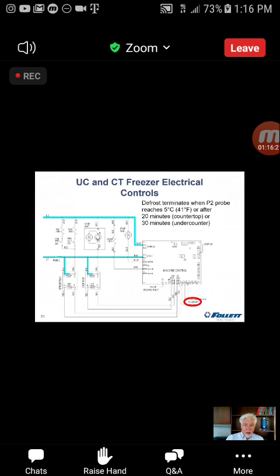Okay. So, like I said, we want to terminate on temperature. It typically takes around 7 or 8 minutes on these units. It should get nowhere near these time limits. So when the probe is satisfied and we terminate the defrost on countertop units only, remember these are the only ones with that evaporator that's on the ceiling of the storage cabinet, the one that's up there. Because of that different design, we go into what's called a drip time.